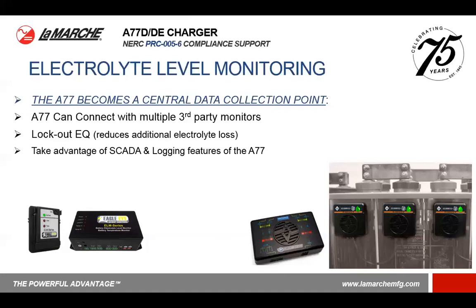For example, if you had a low electrolyte level, not only are you telling the charger to bump out of equalize, but you're also writing a time date stamp on the data log file, and you're also telling somebody who's monitoring the system via one of the SCADA protocols immediately when this event has occurred and when it may have cleared if you have a faulty or intermittent sensor. So by adding the electrolyte level sensor to the A77, you really extend the power of those sensors.